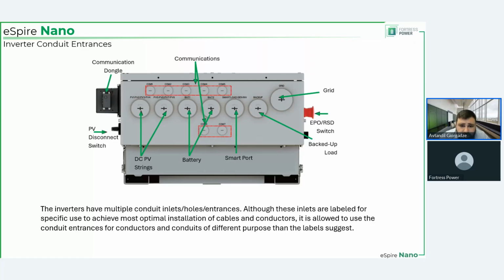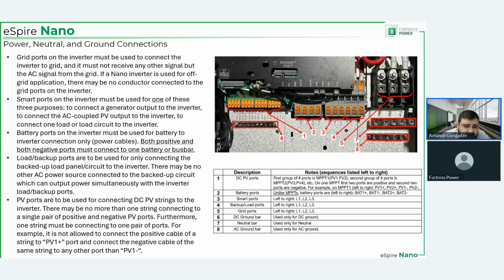Now, the ports, the ones that I mentioned. There's a ton of information on the screen. You can read it, but I will go over them one by one. Let's start with number one, our MPPTs. The extremely observant ones of you will notice that this has 16 inputs, which means it has 4 MPPTs, which means that this is the photo taken of a 60 kilowatt 480 volt inverter, which is true. This is the one that we have in the lab, and it has 4 MPPTs, just like a 60 kilowatt inverter is supposed to. And this is what I meant. You have 1, 2, 3, 4.